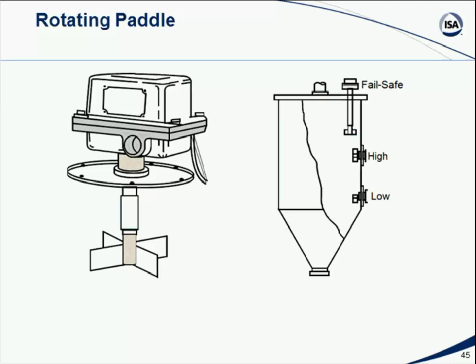And in this particular case, we're showing a type of device called a rotating paddle transmitter. This is actually something where you cut a hole in the tank and you stick the paddle in and you bolt the whole thing up. And this motor drive here turns this paddle slowly. Now, if the paddle is hanging there in air, it's going to keep turning. If you keep pouring stuff into the bin and it builds up and up and up to where it finally covers the paddle, it's on a slip torque system, so the paddle will stop turning, and the motor that's driving it will notice an increase in torque. In other words, the thing's not turning, the shaft's being held, and that increase in torque will be usable as an indicator that the level has at least reached this paddle.